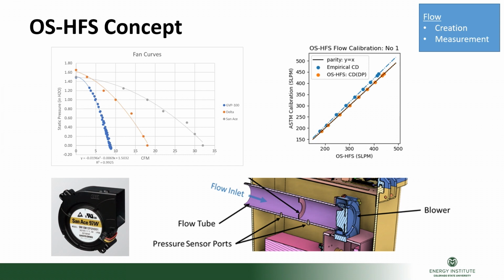We decided to use an orifice plate flow measurement device. Basically, it's pretty simple and well characterized. You can look at an AGA standard or an ISO document, and it sort of just guides you through it. You use the right geometries, and you're going to have a good starting accuracy.